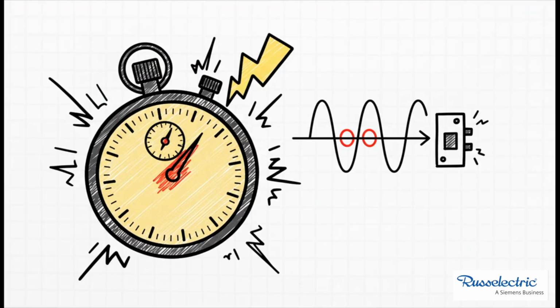This is where we get something called a 3-cycle rating. In our power system, a cycle is just 1/60th of a second. So a 3-cycle rating means a standard breaker trips in about 5/100ths of a second. That's basically instant.